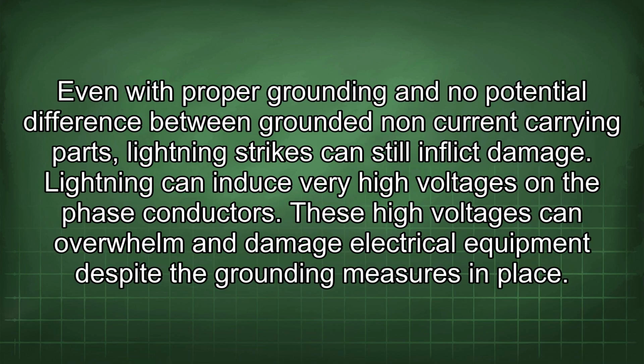Even with proper grounding and no potential difference between grounded non-current carrying parts, lightning strikes can still inflict damage. Lightning can induce very high voltages on the phase conductors. These high voltages can overwhelm and damage electrical equipment despite the grounding measures in place.